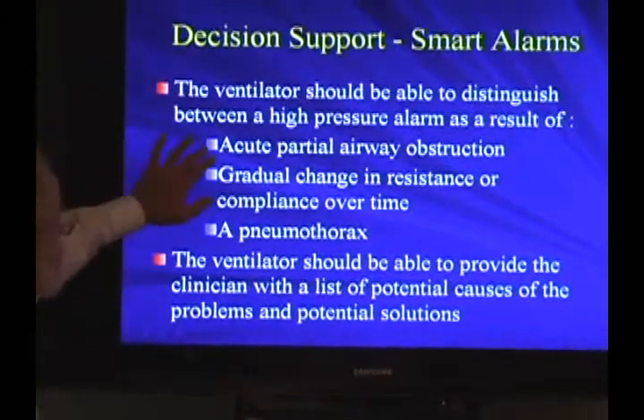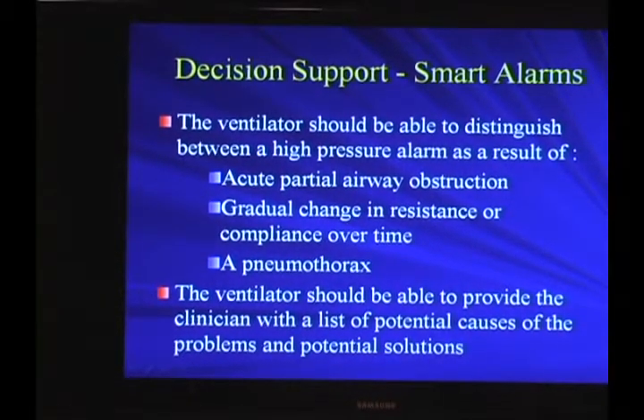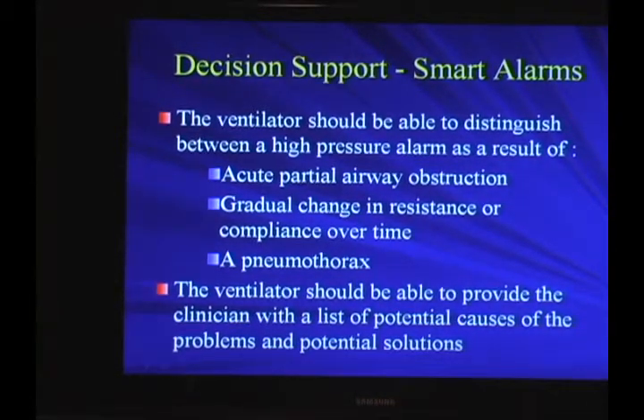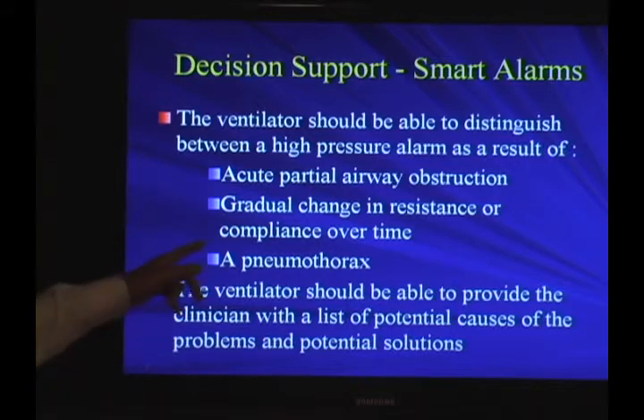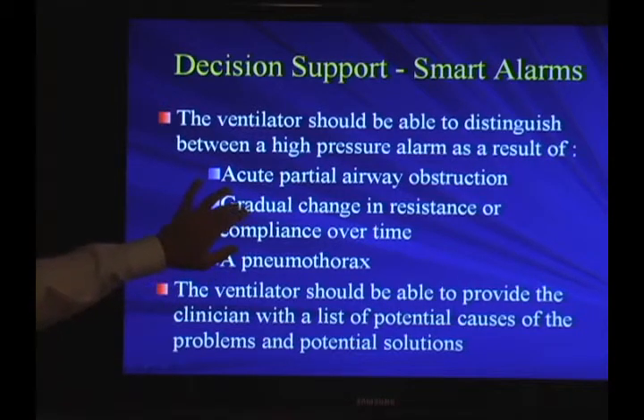If you can do that, I can program the ventilator to identify the same 3 different responses as you would. What I would expect is with the periodic, you've got some water in the tubing, some secretions. Periodically, you're seeing the pressure go up. Not a big deal. Surely you need to correct it, but it's not an emergency. Gradual change in resistance, the slow increase in pressure over hours means you've got a gradual change in resistance or compliance. Something to address, but not an emergency situation.